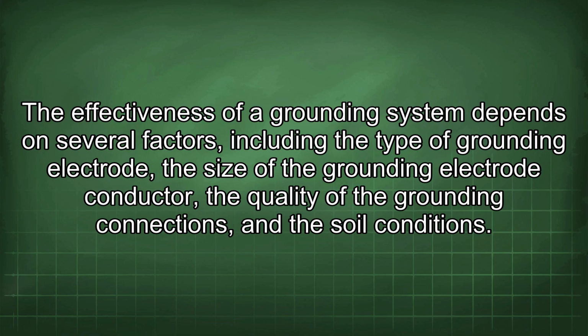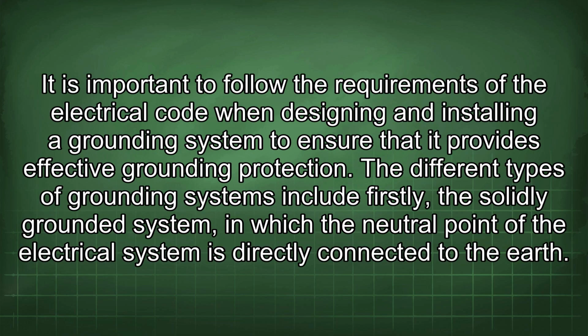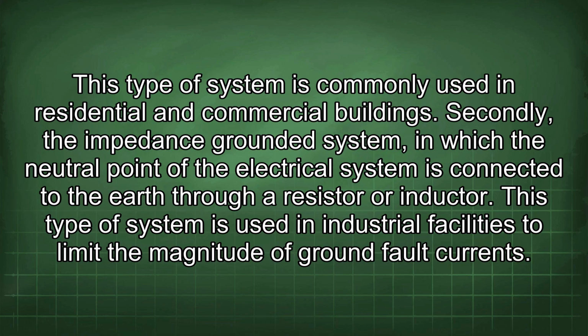The effectiveness of a grounding system depends on several factors, including the type of grounding electrode, the size of the grounding electrode conductor, the quality of the grounding connections, and the soil conditions. It is important to follow the requirements of the electrical code when designing and installing a grounding system to ensure that it provides effective grounding protection. The different types of grounding systems include, firstly, a solidly grounded system, in which the neutral point of the electrical system is directly connected to the earth. This type of system is commonly used in residential and commercial buildings. Secondly, the impedance grounded system, in which the neutral point of the electrical system is connected to the earth through a resistor or inductor.